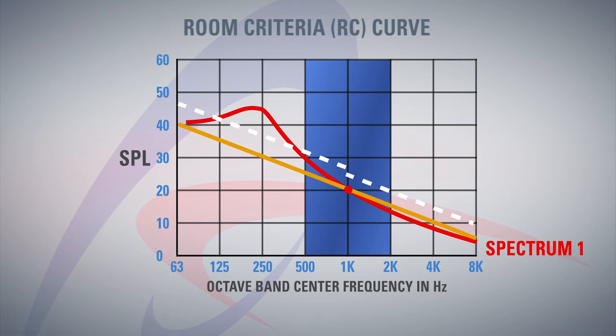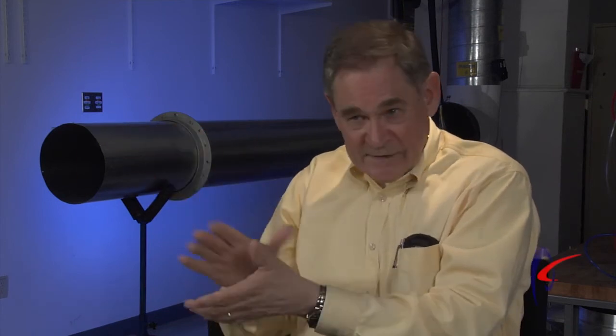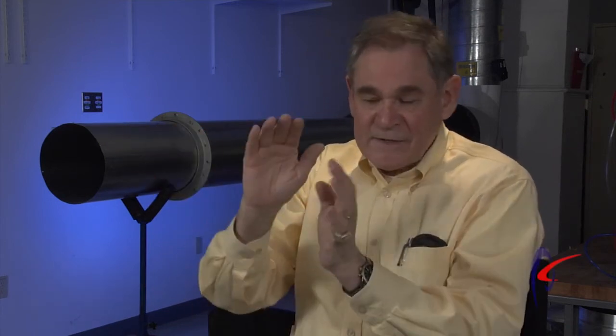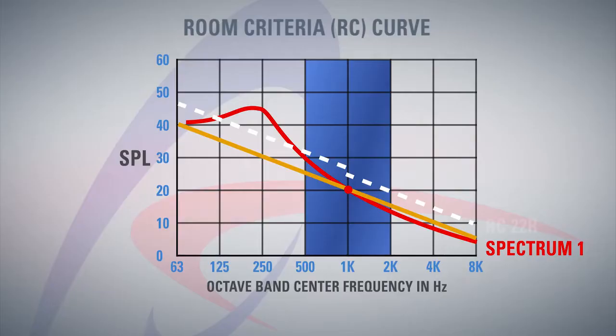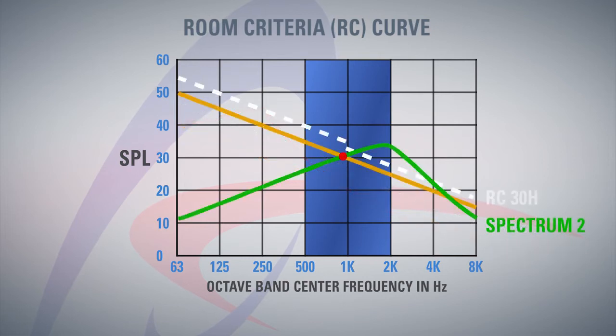Above 500 hertz, the tolerance is tightened to 3 dB, because you're looking more toward the speech interference range and want a tighter tolerance. If you don't exceed 3 dB, you don't have a hissy type system. So this gives you an RC neutral if you didn't exceed any of those tolerances. If you exceed the low tolerance it's going to be RC rumbly; if you exceed the higher tolerance, it's going to be RC hissy. It gives you an indication not only of the overall level as it affects speech communication, but also the quality of the sound.